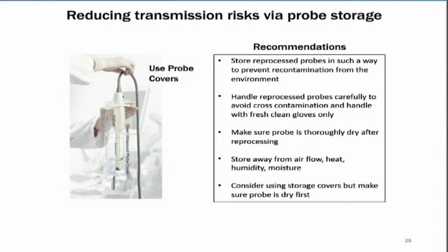So reducing transmission risk via probe storage. This is also important. So the recommendations would be to store the reprocessed probes in such a way as to prevent recontamination from the environment. Handle reprocessed probes carefully to avoid cross-contamination, and handle with fresh, clean gloves only. Make sure the probe is thoroughly dry after reprocessing, and store away from airflow, heat, humidity, and moisture. Consider using storage covers, but make sure the probe is dry first before you put it into the storage.